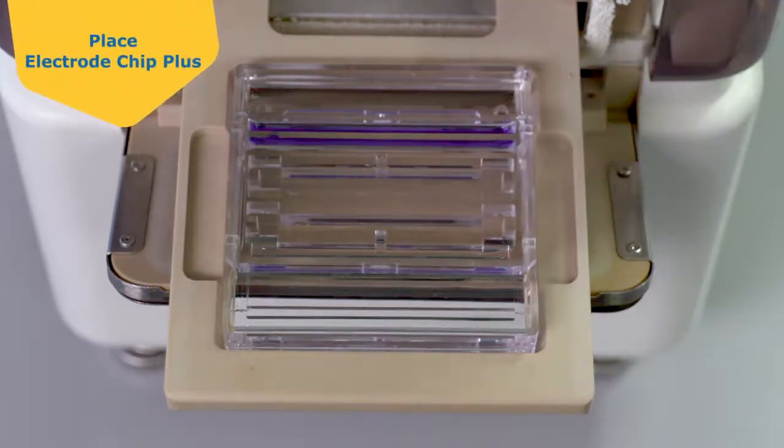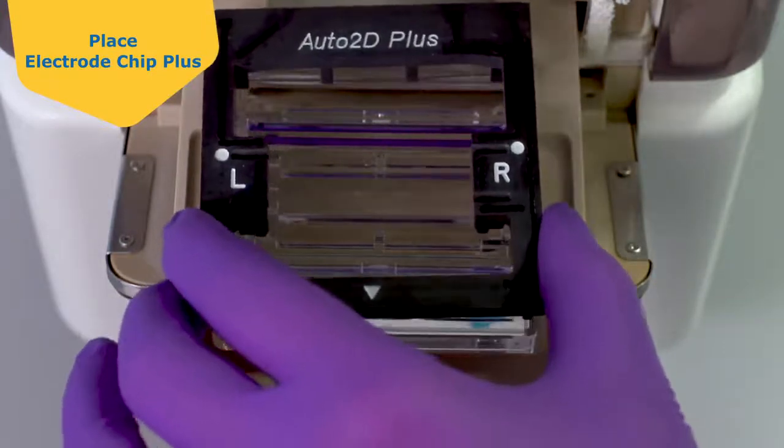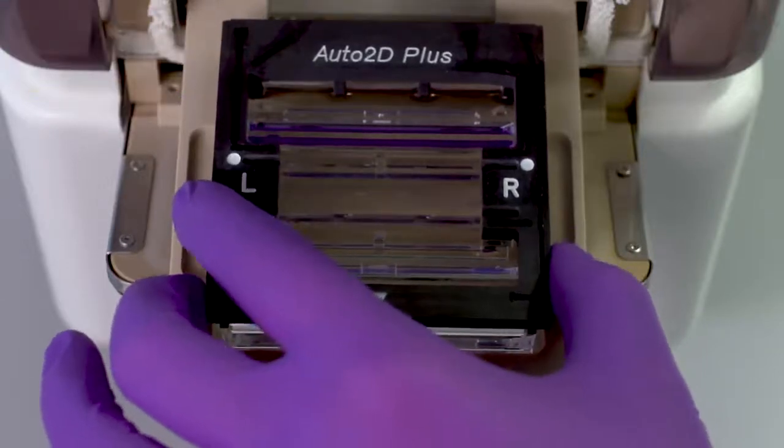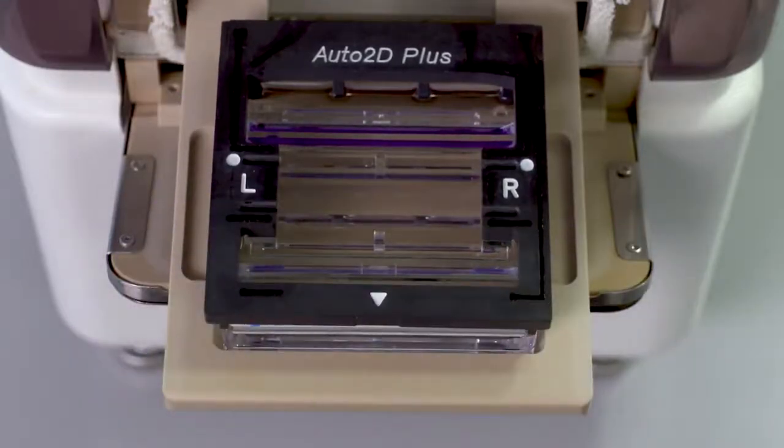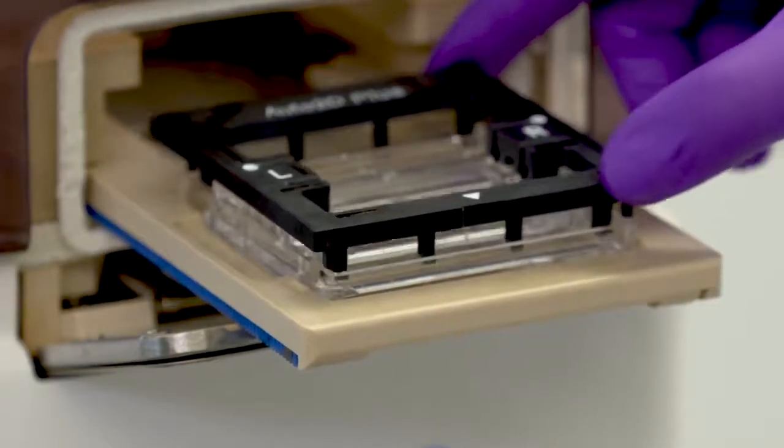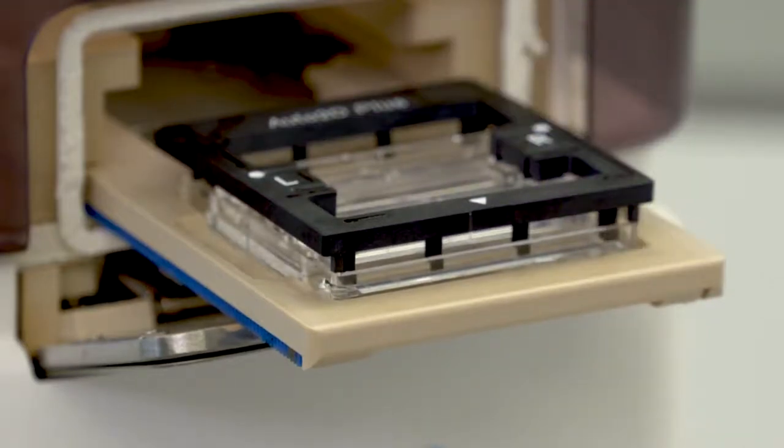Once all solutions are loaded, set the Electrode Chip Plus on top of the Solution Chip Plus with the triangle toward the front of the chip. Make sure that the Electrode Chip Plus is dry before adding it to the chip assembly and is sitting securely on the Solution Chip Plus. This is an example of an incorrect chip assembly. And this is how the chips look when they are assembled correctly.